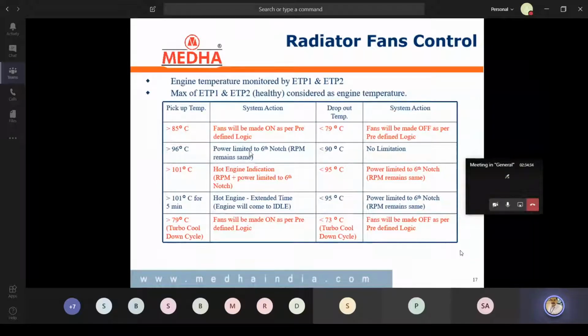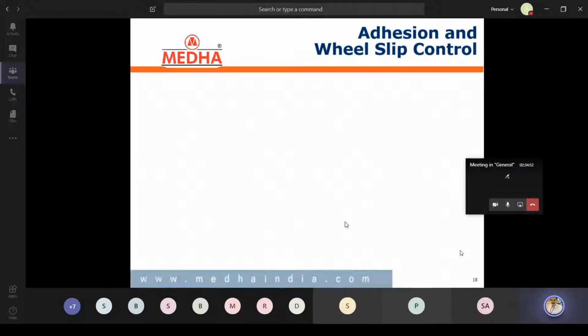And there is a turbo cool down cycle concept. During the turbo cool down cycle, automatically the temperature will come down to 79, not 85. So this hysteresis value is -6. Whatever the pickup value, -6 will be its dropout value. That is about radiator fan control.